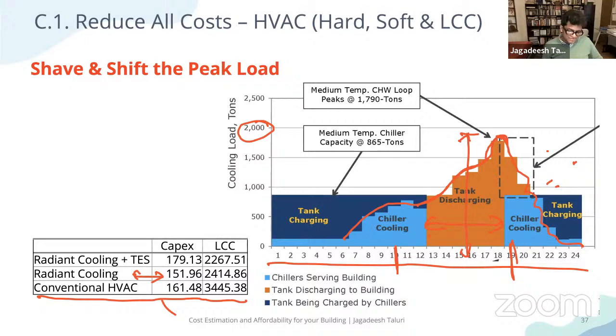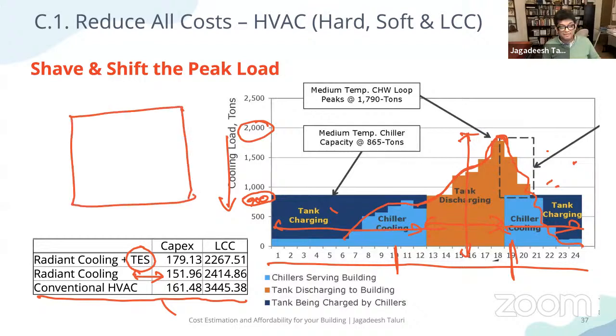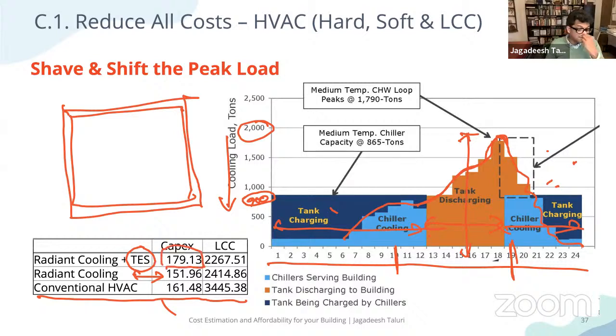So in these scenarios, somebody may suggest making a thermal energy storage tank. We'll run the chillers only during the night, charging the tank with coolness, and during the daytime we'll discharge that stored coolness to run the building. That way, instead of buying a 2000 ton chiller, we only need a 900 ton chiller. You may think you've reduced the chiller size so it costs less, but you're also building a huge insulated water storage tank, with additional piping, maintenance, and other costs. All of this may drive up your capex, say to 179 lakhs instead of 161 lakhs.